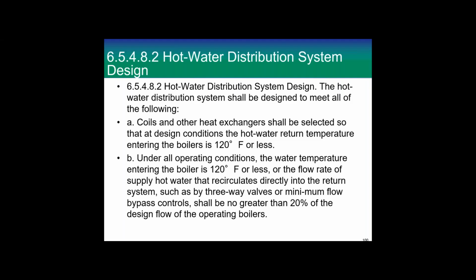So that means that if you send out 140 degree water and you bypass it all, it's going to be tough to get 120 back. So we have to limit that. Condensing boilers don't condense at more than 120 degrees. You're better off if you can get it back at about 100 degrees. You'll get a lot more use out of that boiler as far as savings. Also, some of these numbers you have to be careful with. We are an energy code, and so we don't pride ourselves on it, but we are aware that there's such a thing as Legionnaires' disease.